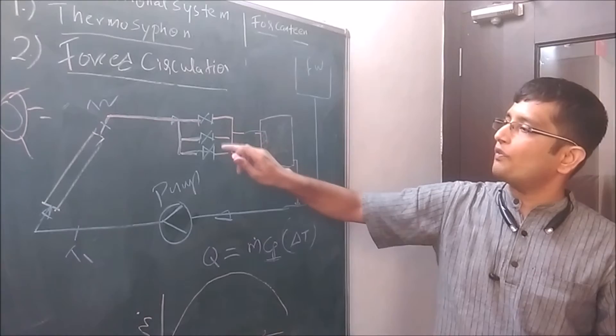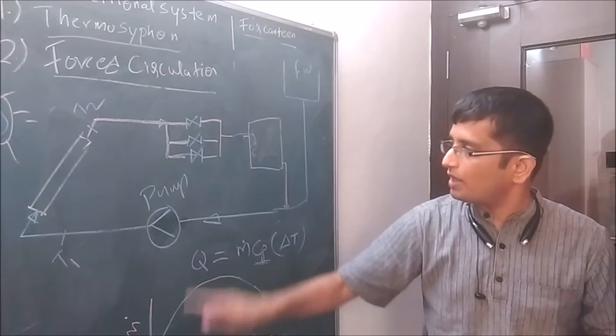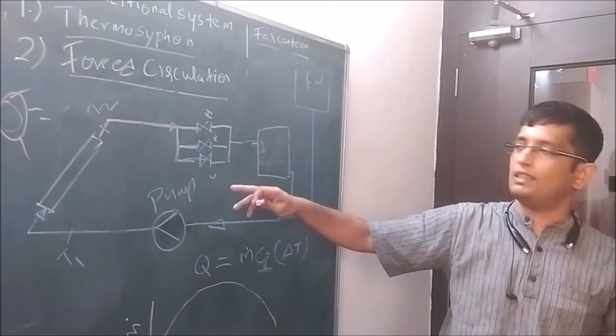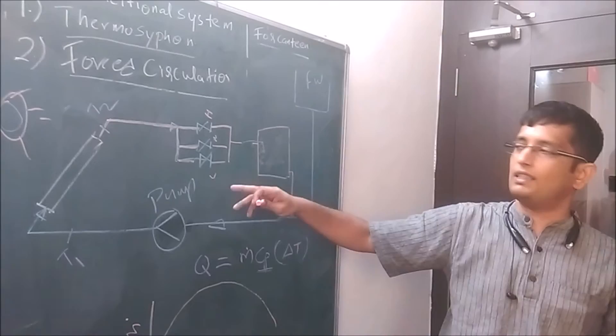How we have achieved this is a very simple innovation that each of these is a flow control orifice so that I have three levels of control. And depending on the availability of heat which is determined by the temperature here, I will be able to select one of these valves to allow the flow rate. So as soon as I select, say for example, the high valve, the medium valve, and the low valve, and a combination of these three, I will be able to deliver the desired flow rate for the desired temperature. So this is our simple innovation in terms of achieving a constant temperature solution.